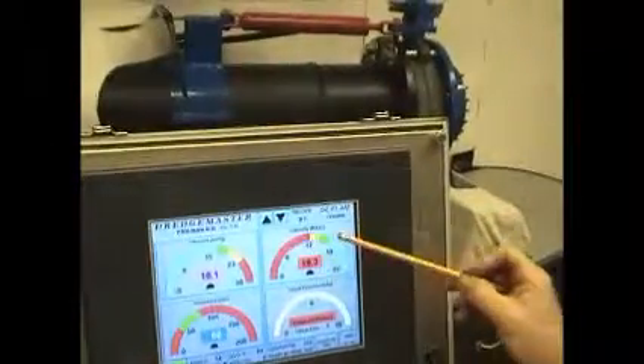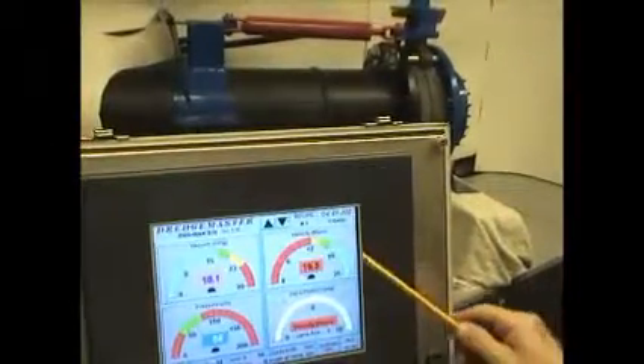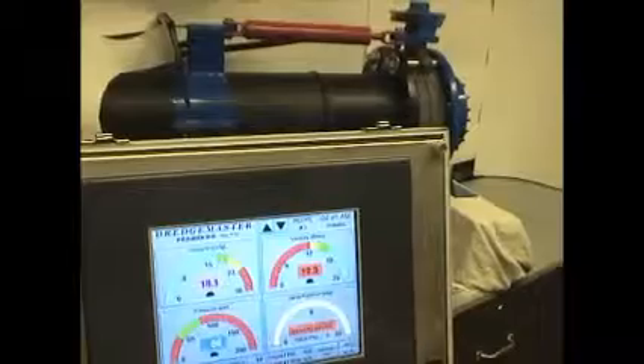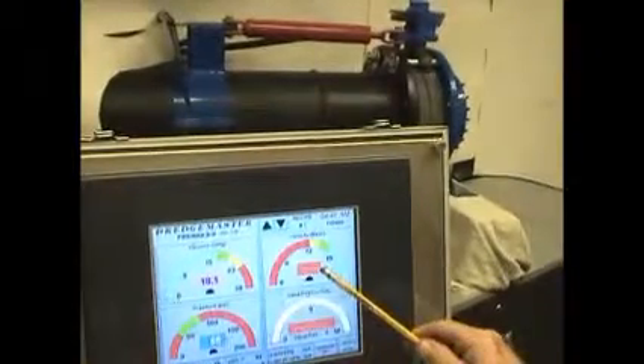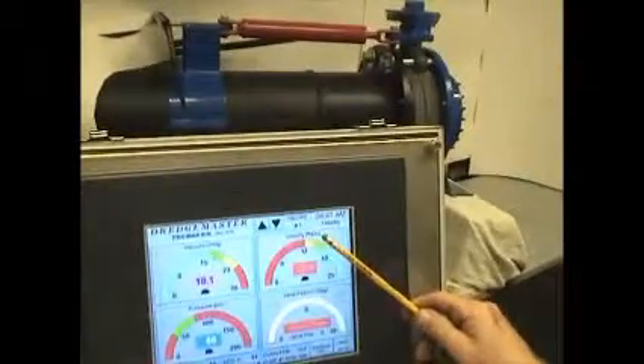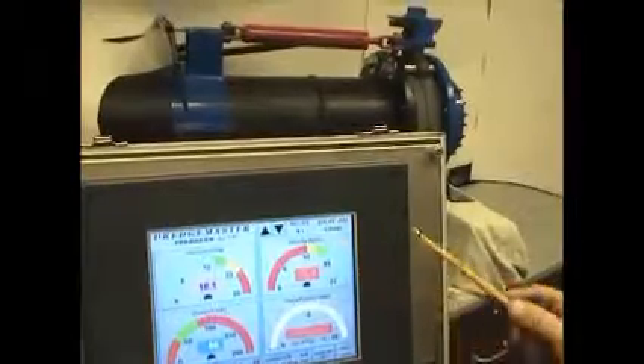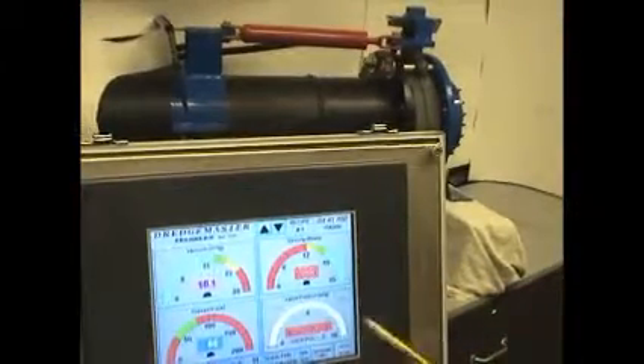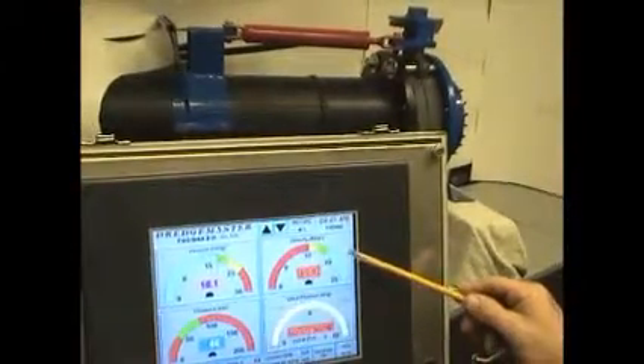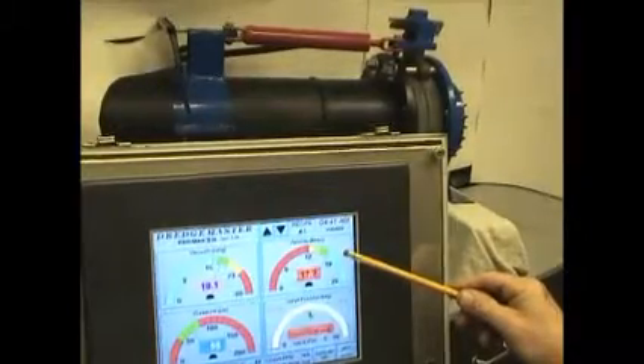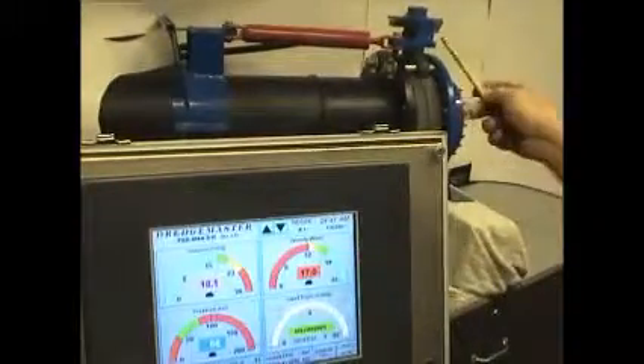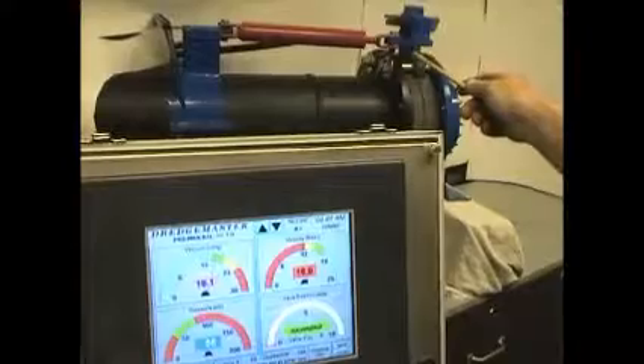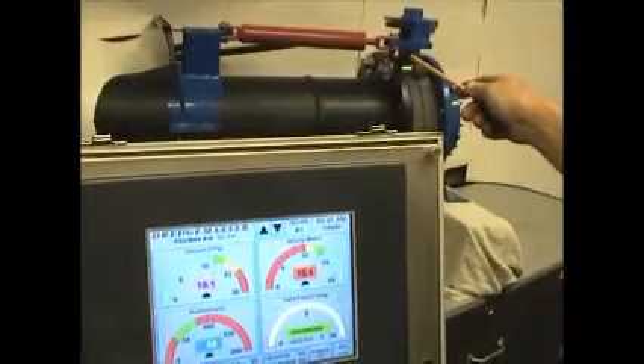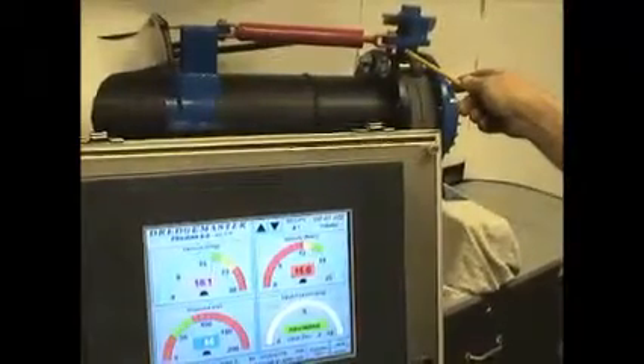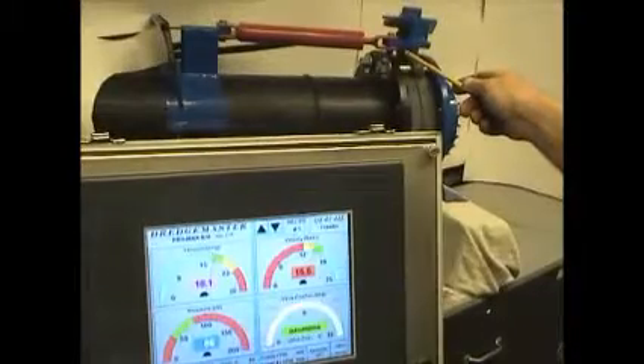The velocity reacts the same way as our vacuum, except with velocity, as our load increases, we start to decrease our velocity, our feet per second or our meters per second. So as we start to load up the pipe, our velocity starts to slowly decrease. Again, the valve is closed because we're in the green and the turquoise ranges. Our valve will remain closed. Our vacuum is steadily dropping.